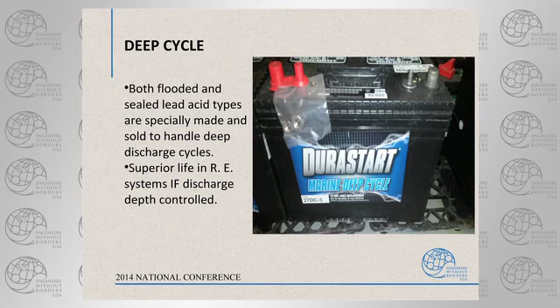Just because a battery says it's good for 100 amp hours, you don't get to use the whole 100 amp hours. It's not like your car's gas tank, where you can drive till the light flashes and says you'd better find a filling station. Don't treat batteries that way, because they won't live long. But anything labeled deep cycle, the manufacturer is claiming he designed that battery to handle a deeper cycle, so you can probably get about 60% of rated capacity out of it.